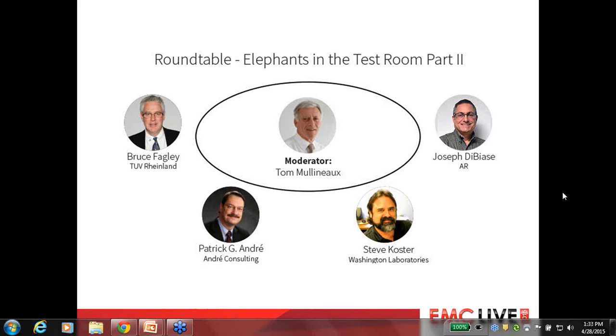As was pointed out by every single member of the panel, actually you don't need the OATS to have accreditation. If you can prove that you can reach a certain standard on any particular test, you'll be accredited for that particular test. But I would put it to you that OATS still has a lot to answer for. It still seems to be the golden reference. It's had an impact on the industry from early days. The reason there are high ceilings in 3-meter chambers to cater for the 4-meter height, born in the OATS setup, just so they can claim equivalence. The fully reflecting floor and the issues that cause is again born of the OATS setup. And test locations way out in the boonies and miles away from transport hubs or airports are there because they're seeking low ambient noise. I put it to you guys that OATS still has a lot to answer for, although I do retract the case that you need them for accreditation.